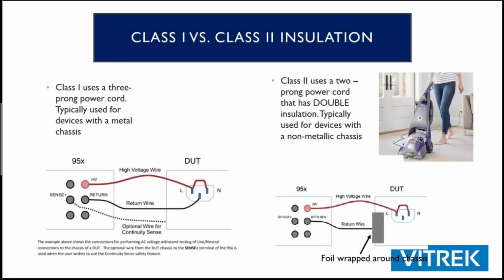All right, so we're coming back to what we talked about earlier, which is class 1 versus class 2 insulation. And there's a very different way in how these products are tested. Class 1's going to be the easiest. You have this metal chassis, which is isolating the operator from the product and maintaining connection to ground. In that case, it's really straightforward. You're going to connect line and neutral to our high voltage output. The return is going to go to chassis, and then the return would typically go to earth, and then you're going to have the continuity sense plus lead going to chassis. Very straightforward to hook up.